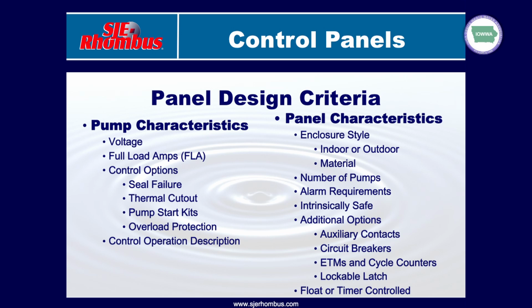Control options. Some of your higher horsepower pumps are going to have options available on that, like a double seal pump. A lot of times will have a seal fail indicator that lets you know one of your seals have gone bad inside the pump before it causes catastrophic failure of the motor. We can incorporate seal fail circuitry into the control panel so you get either an audible and visual alarm or a light that comes on that says, hey, seal number 1's failed. Go ahead and get the pump rebuilt before you have, again, catastrophic failure.